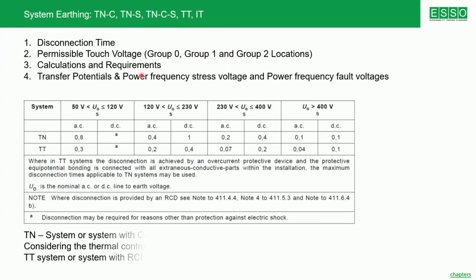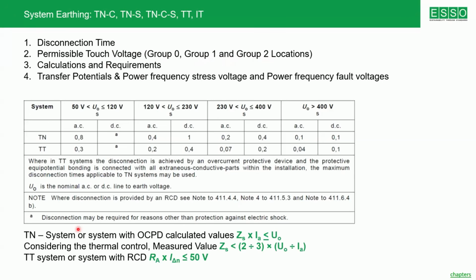Then there are certain calculations. Example, in case of a TNS system, and if you are using OCPD for the automatic disconnection, then you know very well the Zs calculation, the fault loop impedance calculation. Considering thermal control, there is a calculated value of fault loop impedance, and there is a measured value of fault loop impedance.